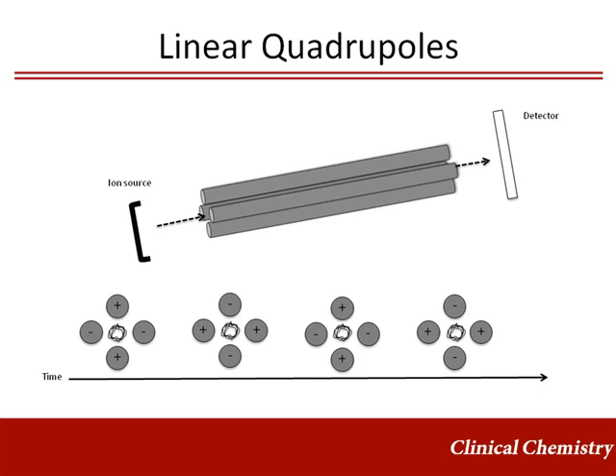Linear quadrupoles have four parallel rods arranged in a square formation. At any given time during the analysis, one set of diagonal rods is positive while the other diagonal set is negative. Which set is positive and which set is negative alternates back and forth during the analysis. For an analyte at a known mass-to-charge ratio, the amount of positive or negative charge and the frequency at which the diagonal pairs switch their sign is optimized to produce a successful ion flight path through the quadrupole.